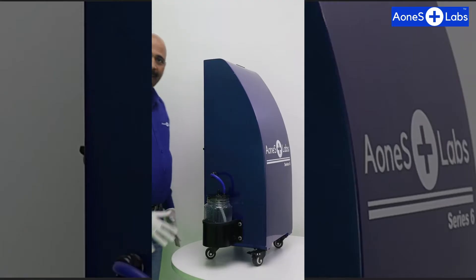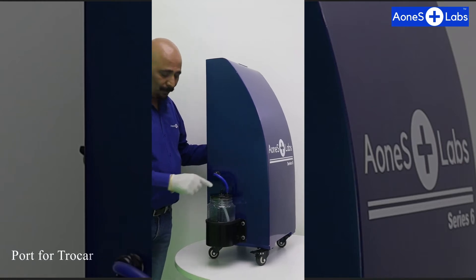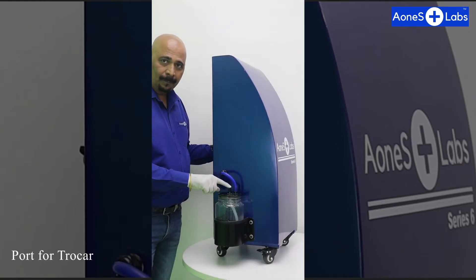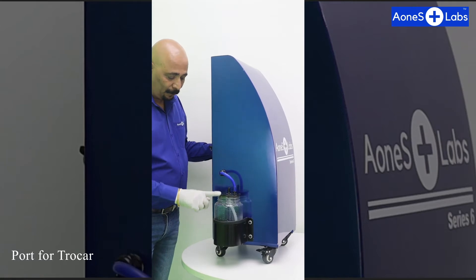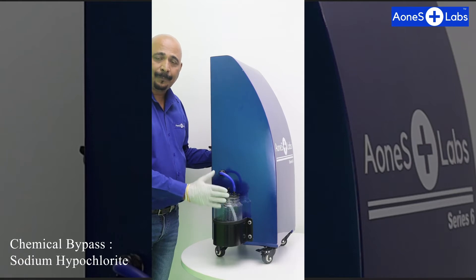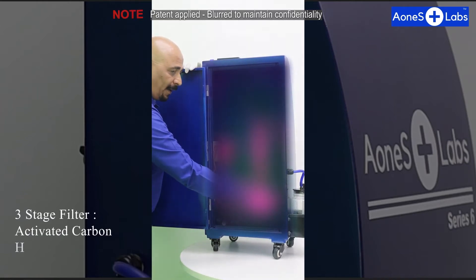Let's take an example of a laparoscopic surgery. The trocar coming out from the patient is connected here, and the gas completely flows through this bottle which is filled with sodium hypochlorite - this is the start of the disinfection process. The next step is that the smoke passes through this chamber, which consists of a three-layer filter containing carbon particles, HEPA, and a ULPA layer.